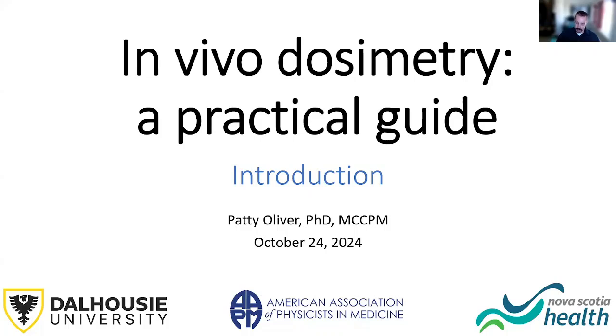We partly organized this webinar in response to the Landauer OSLD recall. The recall notice was issued in July 2023 because it was found that some of the dosimeters did not meet the accuracy specifications of ±5%. There are other OSLD manufacturers, so this webinar still discusses the use of OSLDs as well as possible reuse of the dosimeters. We also give other options for in vivo dosimetry, including TLDs, EPIDs, scintillators, reusing OSLDs, etc.